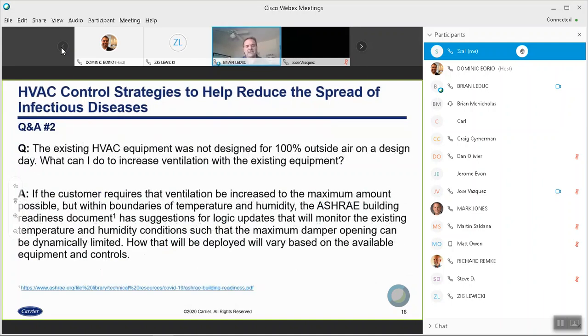decisions to be made. Question 2, again, as I said, I'm going to probably hit this point more than once. The existing equipment is not designed for 100% outside air. What can I do to increase ventilation with the existing equipment? Obviously, without mechanical changes, there's not much you can do. If the customer requires ventilation to be increased to the maximum amount possible, but within the boundaries of temperature and humidity control, the ASHRAE building readiness document does have a suggestion for some logic updates that will monitor the existing temperature and humidity such that the maximum OA damper opening can be dynamically limited.